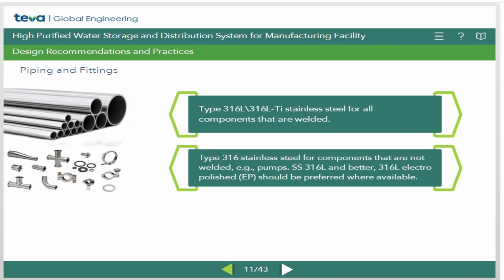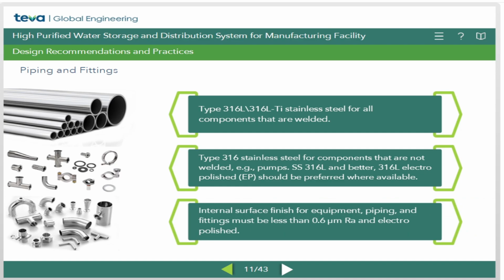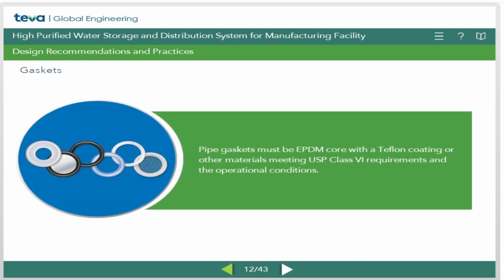For example, pumps. SS 316L and better. 316L electropolished should be preferred where available. Internal surface finish for equipment, piping, and fittings must be less than 0.6 micrometers RA and electropolished. Pipe gaskets must be EPDM core with a Teflon coating or other materials meeting USP Class 6 requirements and the operational conditions.